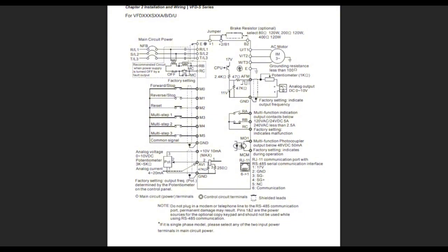So this is our VFD's architecture. The first thing is the main supply, the main power. The VFD runs on three-phase, but you can connect a single phase as well. If you want to control the VFD using a single phase, you can do that. In that case, as you can see here, if you are only using this VFD for a single phase, use any two of the RST terminals. Otherwise, if you're using it for three-phase, you connect the three phases directly to the RST terminals.